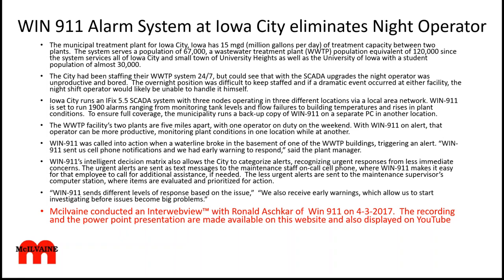But what I would say there is that the next level for the Win 911s and the others is to construct these systems so they are more sophisticated, and the owners as well as the suppliers are thinking in terms of not only alerting the first level of decision makers should there be a problem, but also connecting the suppliers of the aerators, the sludge presses, the clarifiers, and all these other pieces of equipment in the plant, because obviously, like they're saying here, the night operator was unproductive and bored, and the overnight position was difficult to keep staffed, and if a dramatic event occurred at either facility, the night shift operator would likely be unable to handle it himself.